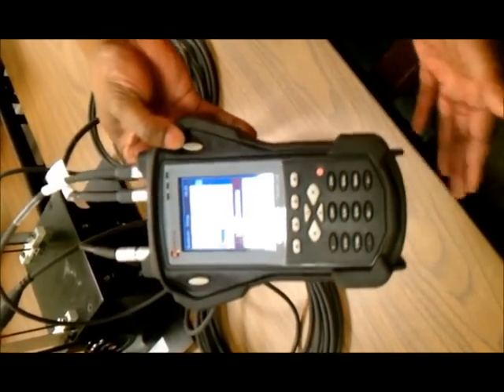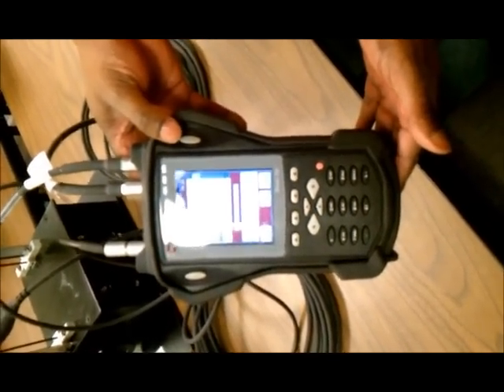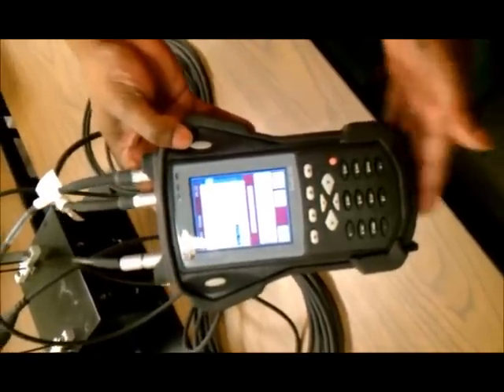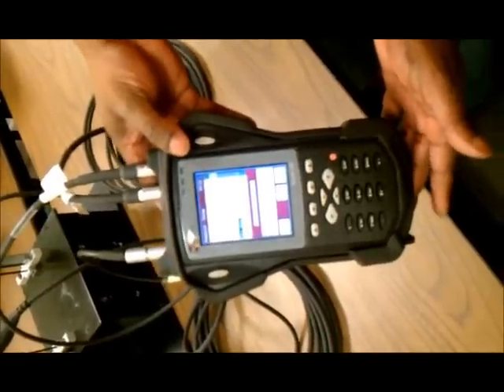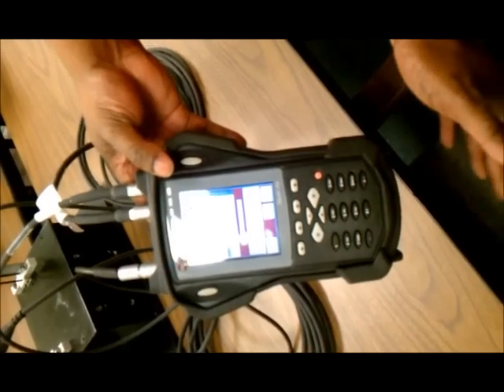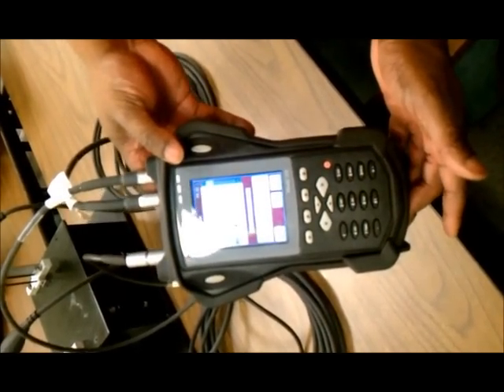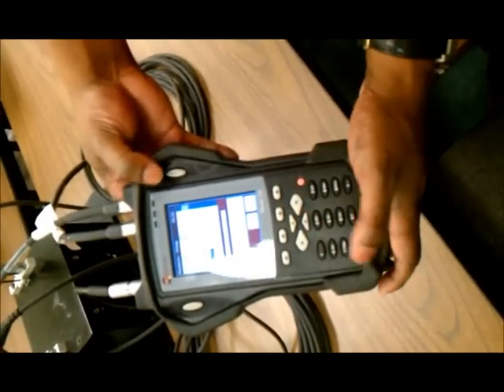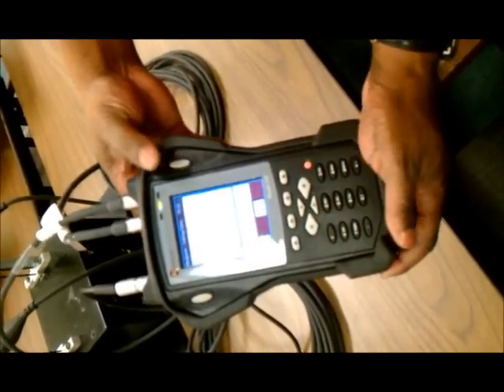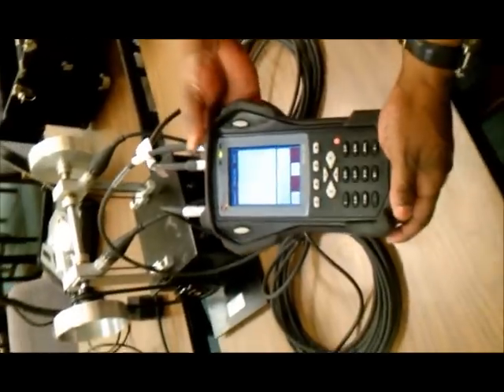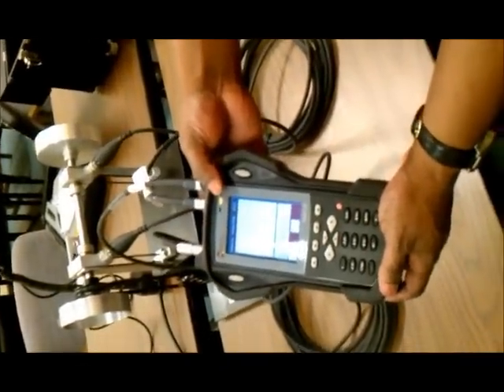And the next part that will be of interest is how we're going to view the signal, whether it's just spectrum, the graph itself, or if it's spectrum and phase angle. For the spectrum, you just use one channel. For the spectrum and phase angle, you'll have to use two sensors. Your second channel sensor will be used as a reference point. So in this case, we'll leave it at spectrum and we'll start it. And what it's doing right now is acquiring data to make our graph.